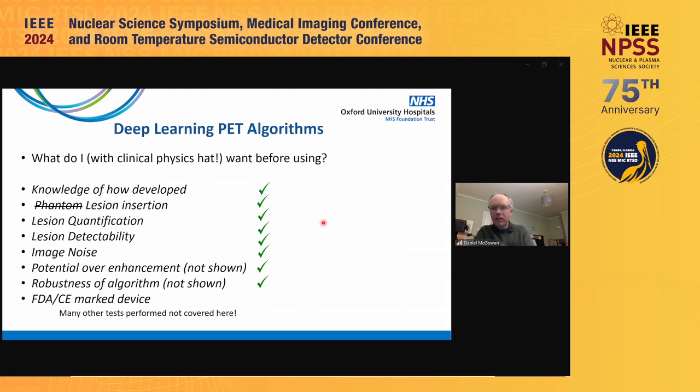So in terms of putting the clinical hat on for these sort of algorithms, we know how it's developed. Rather than the phantom, we've gone for a lesion insertion technique, looked at lesion quantification, detectability, image noise. Another thing I didn't show here in the interest of time, but it's worth thinking about, is potential over-enhancement. You want to be sure these algorithms don't over-enhance the images. In this particular case, you can know mathematically what gain you'd expect from going from non-time-of-flight to time-of-flight, so there are basically guardrails ensuring that you don't go above that.